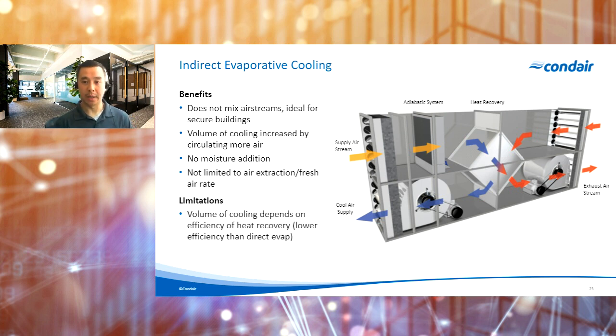Now, the amount of cooling that we can achieve here can be increased by circulating more air, and we're not really limited here to the extraction or the fresh air rates like we would be with a direct cooling system. The thing to keep in mind here is that the efficiency of this type of system can also be increased if we were to put a direct evaporative cooling on the cool air supply as well. So effectively an indirect-direct type system. So generally this type of system will also have a higher cost compared to a direct evaporative application. And the efficiencies here will depend on the efficiency of that heat recovery system as well.